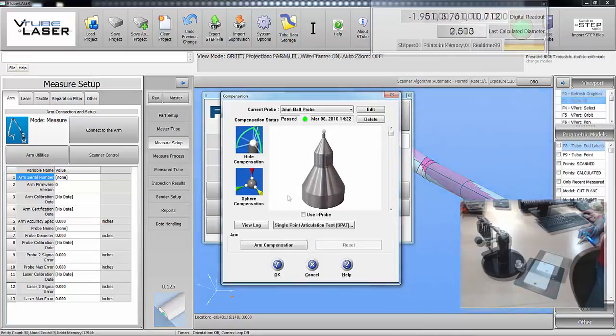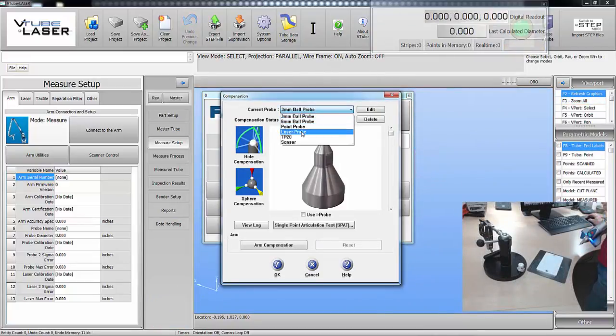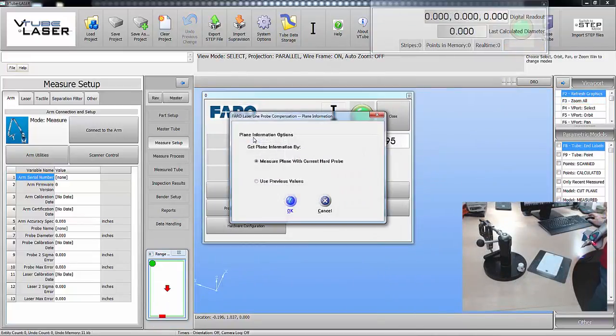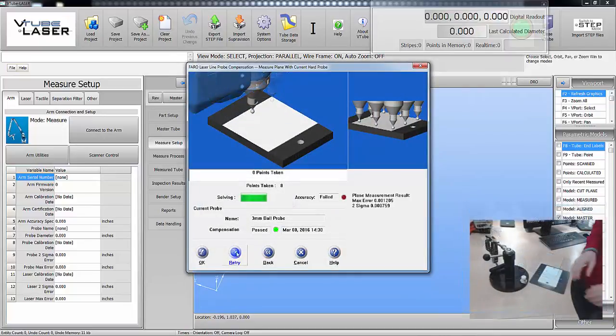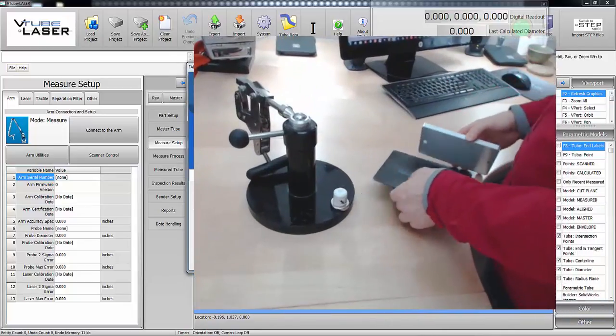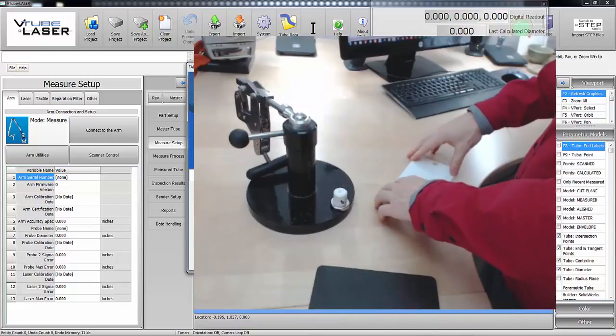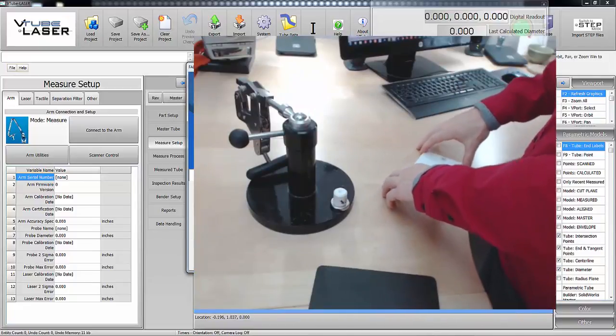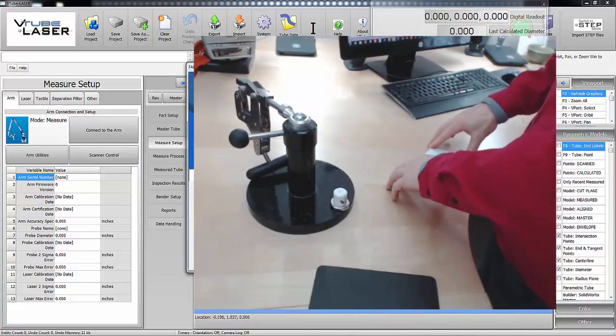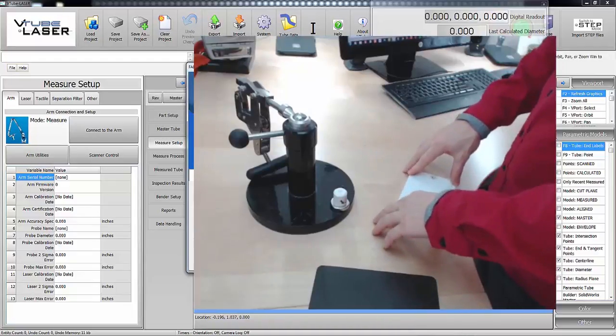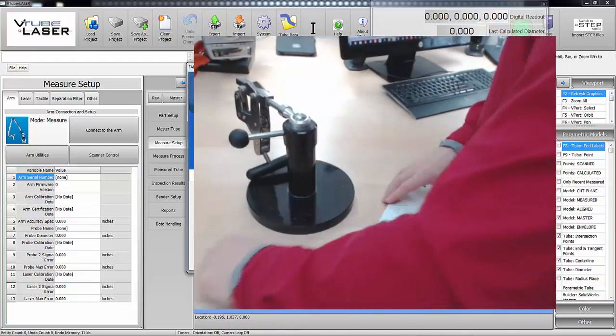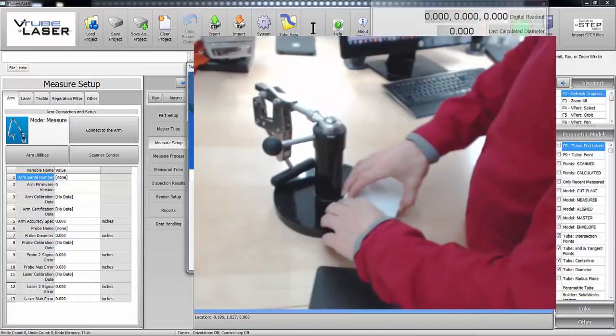Now we're going to calibrate the scanner or the laser line probe. We'll use plane compensation, and we'll indicate that we need to measure the plane. The FARO laser line probe calibration parameters are very strict. If the white plate moves at all on, for example, an office desktop like this, then you'll have to move that calibration plate onto a very flat surface, like I'm doing here.